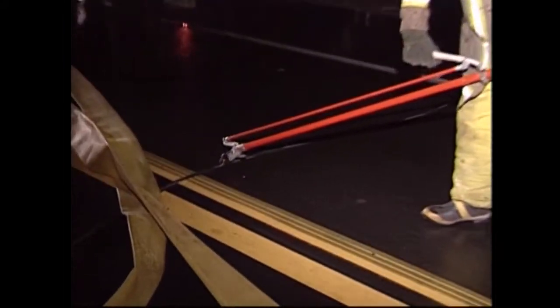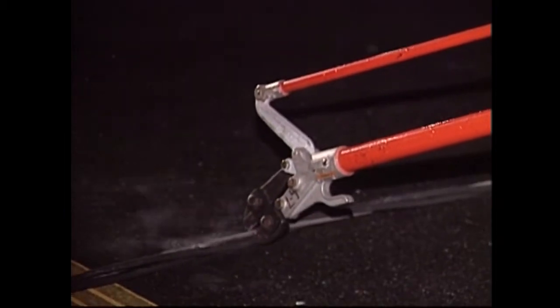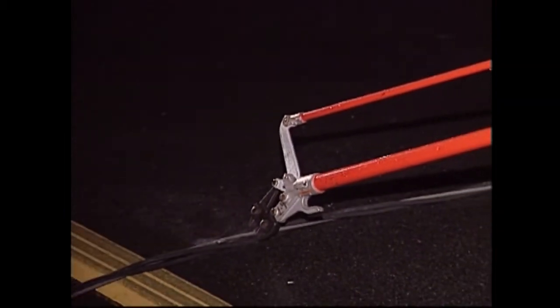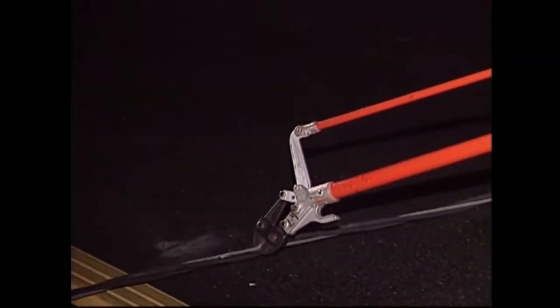What you want to do, if possible, is locate the main breaker box or panel and shut off the power from there. And when doing so, turn away from the power source to avoid being injured if it arcs. All electrical wires are approached as if they were energized. And as shown earlier, even if coated, don't make the mistake of thinking that means they are insulated.